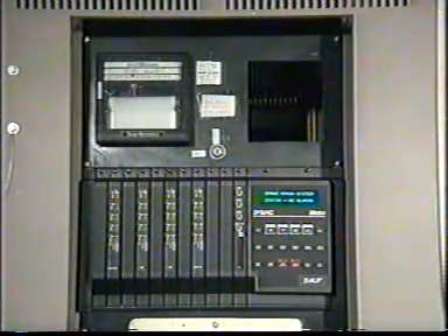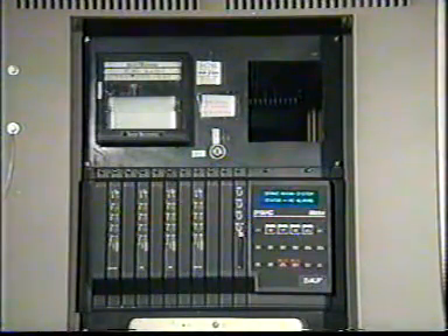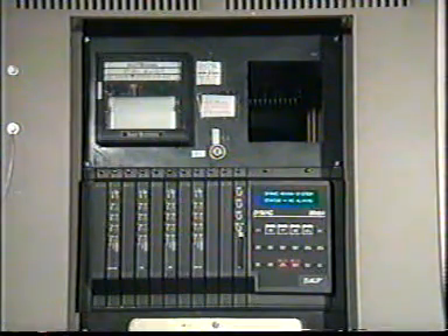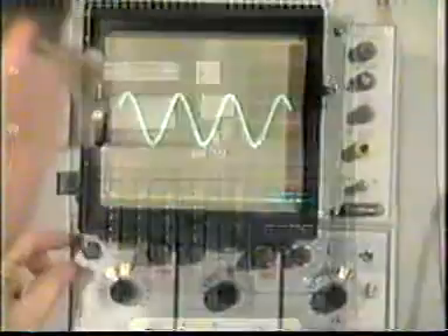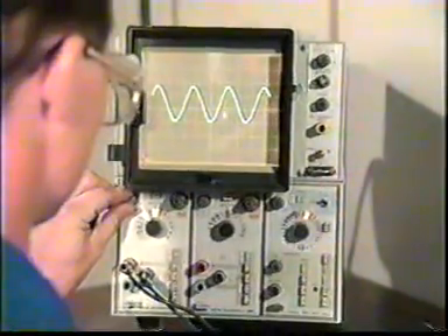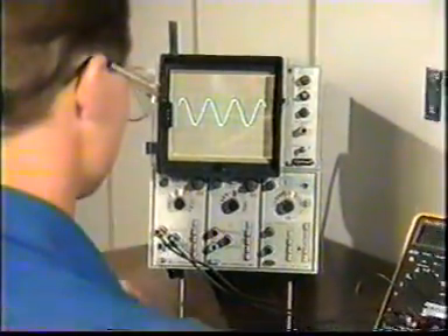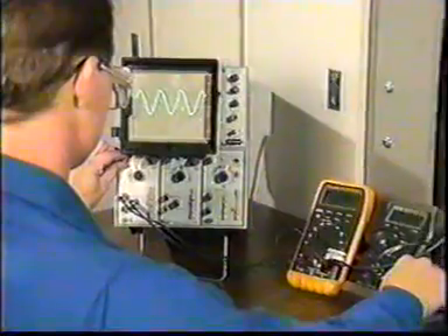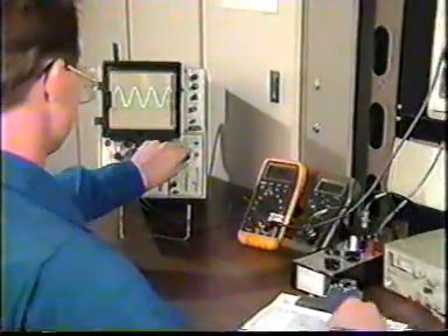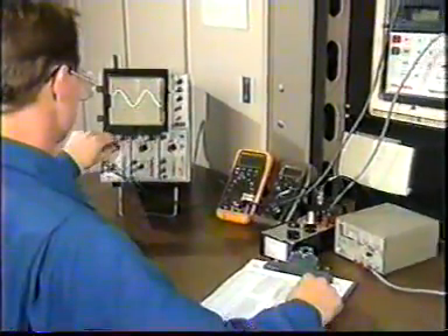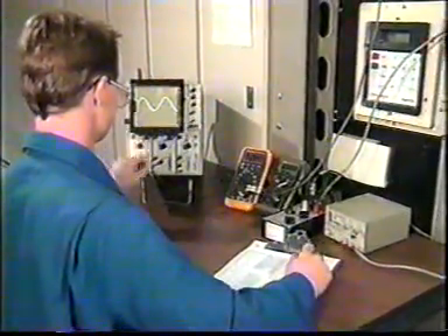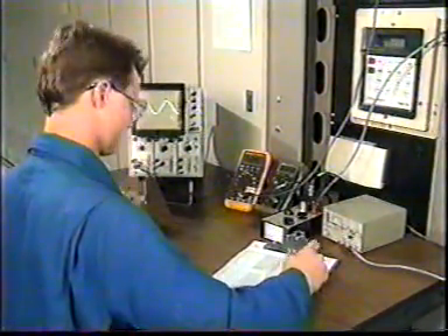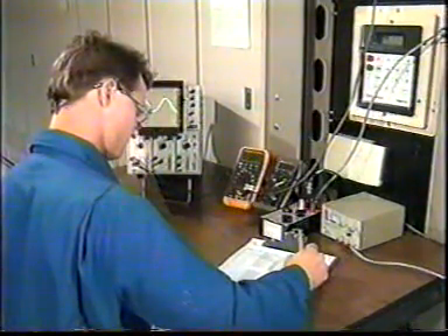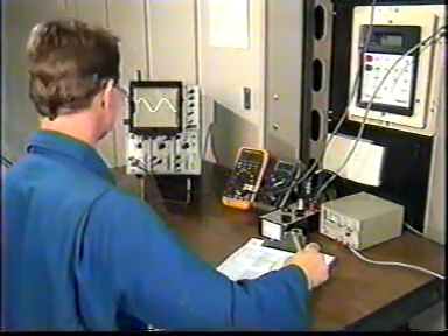Monitors provide indication for shaft vibration. These devices usually contain all the electronics needed to amplify the very low-level signal from the sensor and provide an indication. Calibrate monitors periodically to ensure that the incoming signal provides the proper output indication. Many monitor systems provide auxiliary outputs. These outputs may provide analog or digital signals for use with DCS, remote annunciators, process controllers, or recorders.